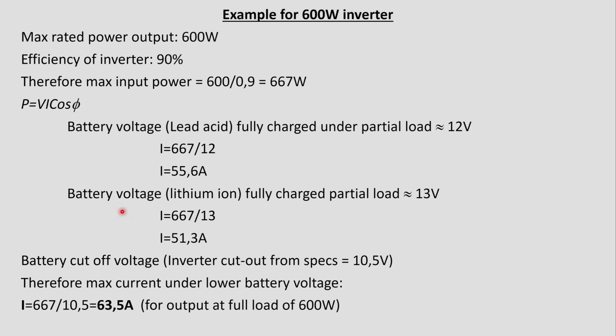Now, comparing that to the lithium ion battery, and let's just say it's at 13 volts. Lithium ion batteries tend to be at a slightly higher voltage than the lead acid. Now, notice that the current required from the lithium battery is a bit lower than the current required from the lead acid battery. But we need to determine a protection circuit that will cover both setups. So now let's look at worst case scenarios, because that's what we protect for. We protect for worst case scenarios.